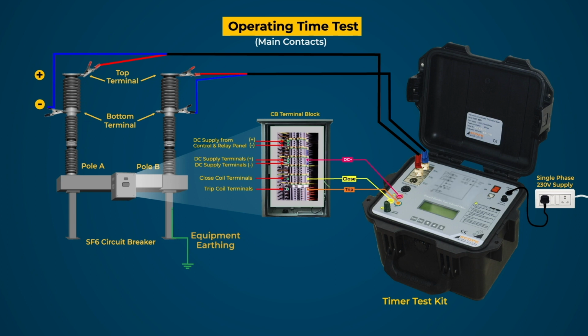Also, connect the master earthing terminal of the tester to the equipment earthing. Check all the connections and the setup is ready to perform the test. Now, select the operation of the breaker and perform the test.